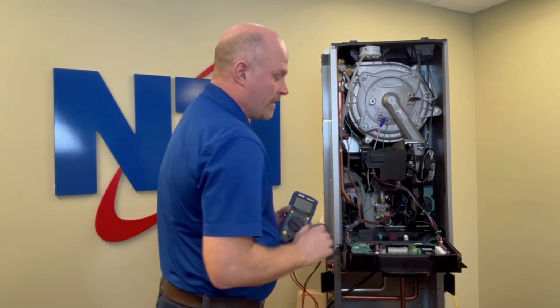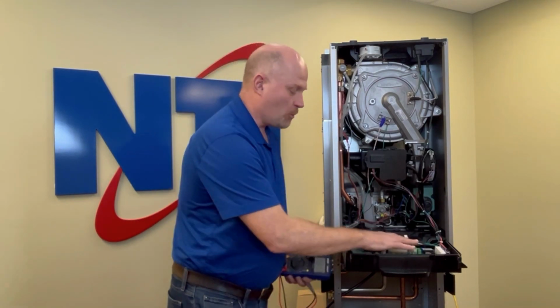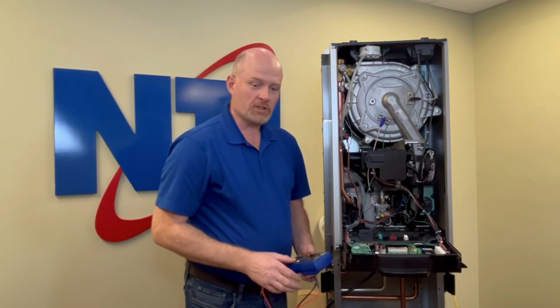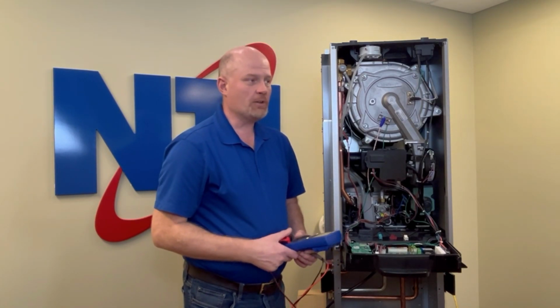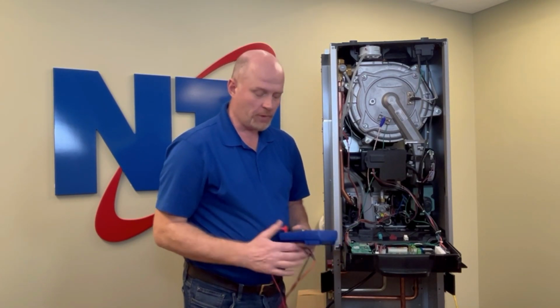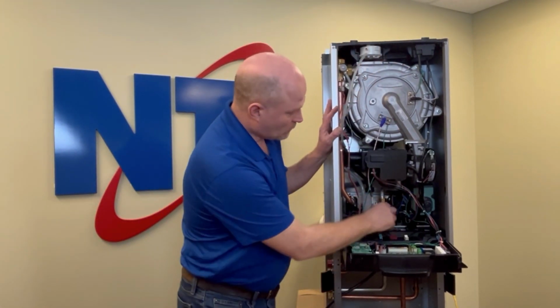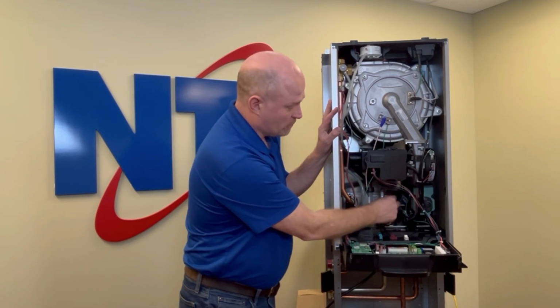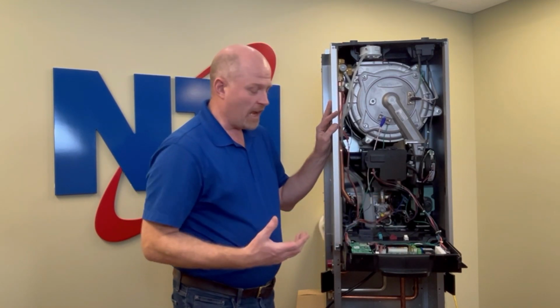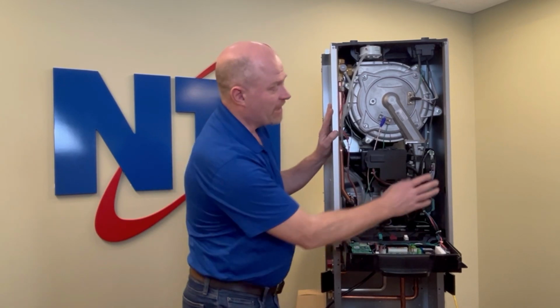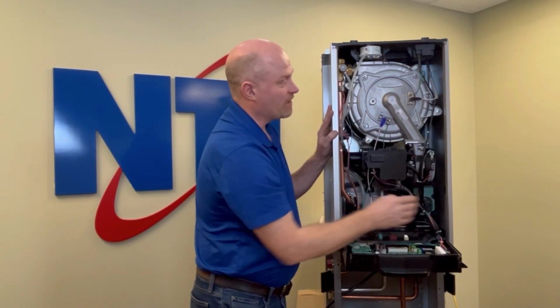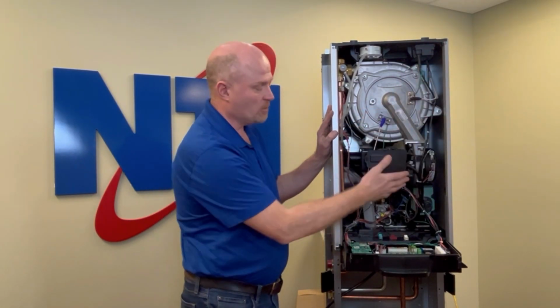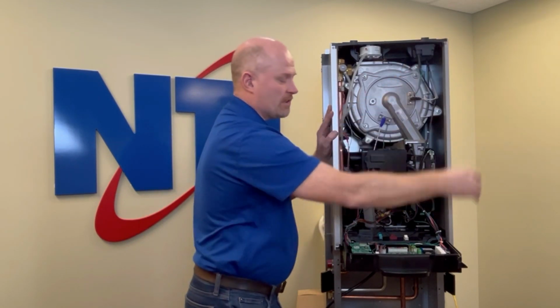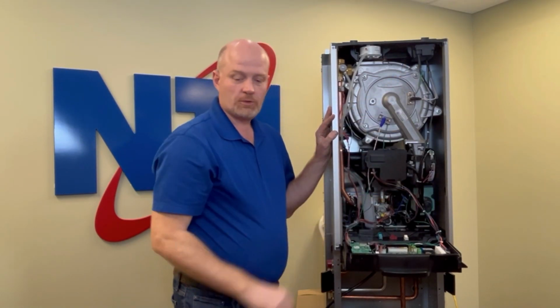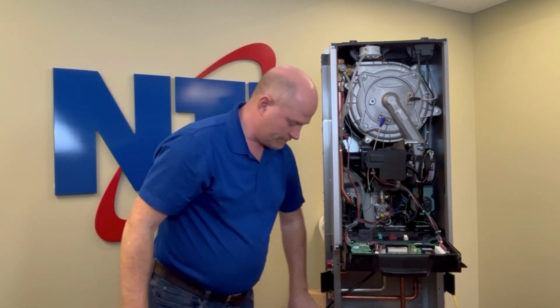If your voltage check is okay, at that point we would typically find that the control board is bad. There is one exception to that though, and that is error code 303. Error code 303 is often caused when the water pressure switch that's connected to the boiler gets wet or damaged in some way. The easiest way to access that switch, if you have a TRX 150 combi or 120 like the boiler in front of me, is to loosen the side panel and then remove the wires from the switch, so we'll show you how to do that next.